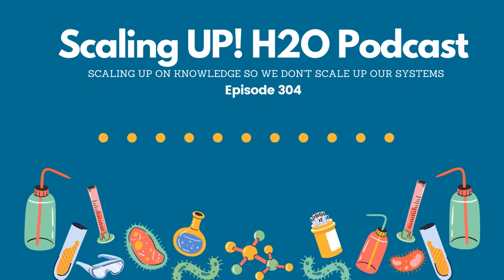I set them all out flat on our bench, and then we have to use the envelopes that you gave us to identify the serial number to the coupon, and then we start weighing each coupon, again, down to the 10,000th of a gram. That's very, very specific, and of course, that's not your ordinary scale. These are special metallurgical scales, and then once that's done, we take a final picture of what that coupon looks like front and back after it's cleaned, and then we start doing math. We do the equation to figure out how many mils per year was lost during that exposure time. And again, a mil is 1/1000th of 1 inch. And then we go ahead and write our reports.